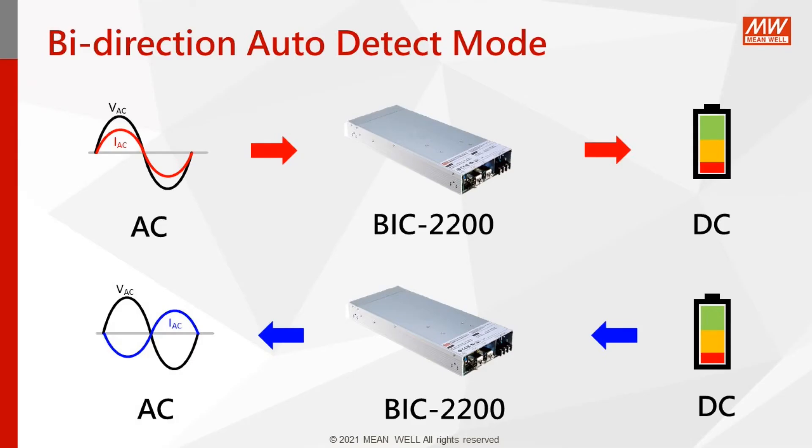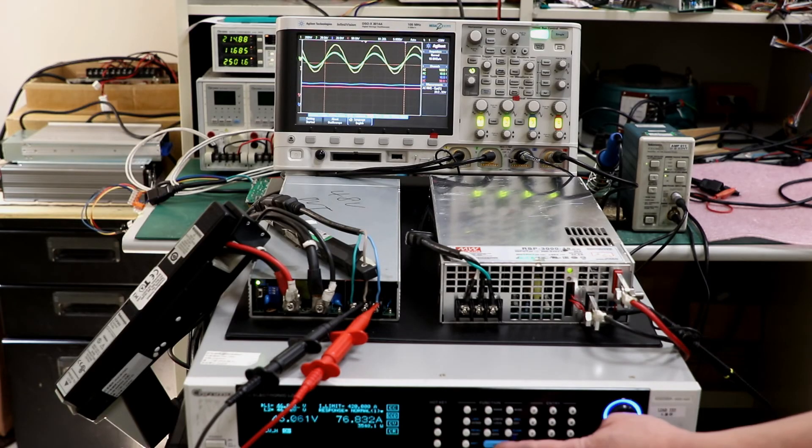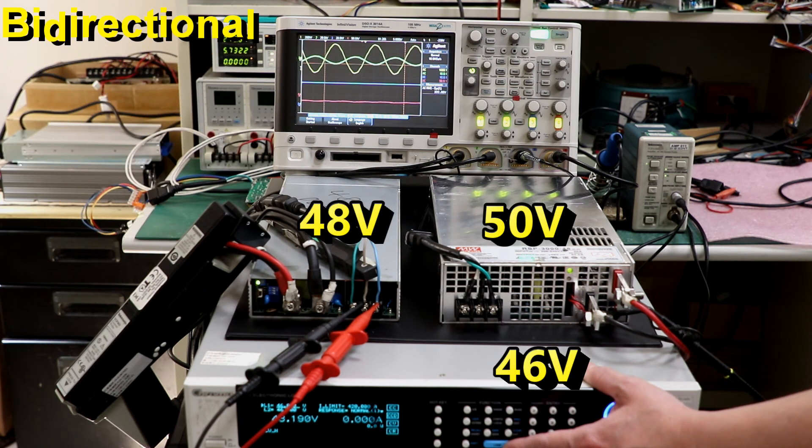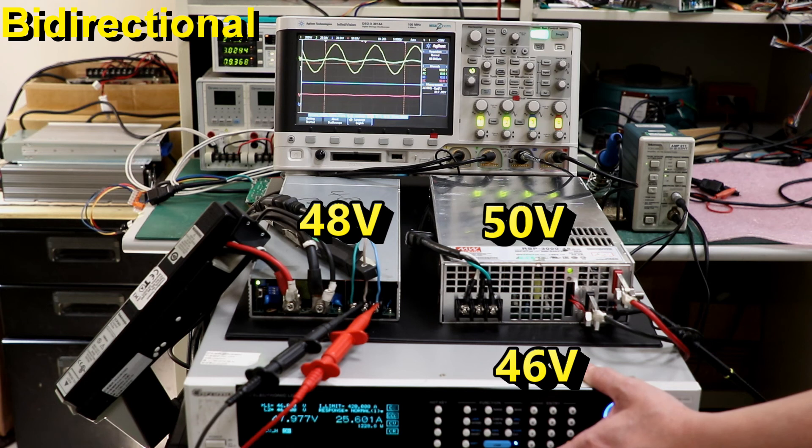And finally, demonstrating the whole function of the bi-direction auto-detect mode. At this time, we connect a DC electronic load set at CV mode and 46 volts and a RSP-3000 with 50 volts to the BIC-2200, 48 volts at the same time.